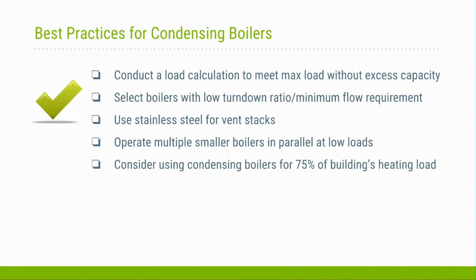Using stainless steel for all the vent stacks is a must, because the condensing of the flue gases creates a corrosive environment, and so you need the stainless steel. That is one of the things that adds to the costs of these boilers, but it's a must. I already touched on operating multiple smaller boilers in parallel, and then consider addressing most of the building load with these condensing boilers, to maximize your economic investment. Next one down.